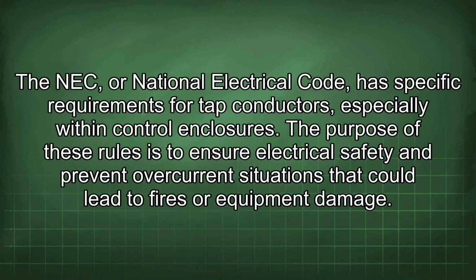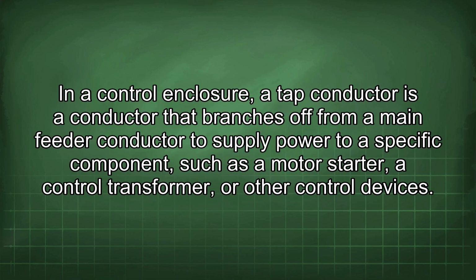The NEC, or National Electrical Code, has specific requirements for tap conductors, especially within control enclosures. The purpose of these rules is to ensure electrical safety and prevent overcurrent situations that could lead to fires or equipment damage. In a control enclosure, a tap conductor is a conductor that branches off from a main feeder conductor to supply power to a specific component, such as a motor starter, a control transformer, or other control devices.